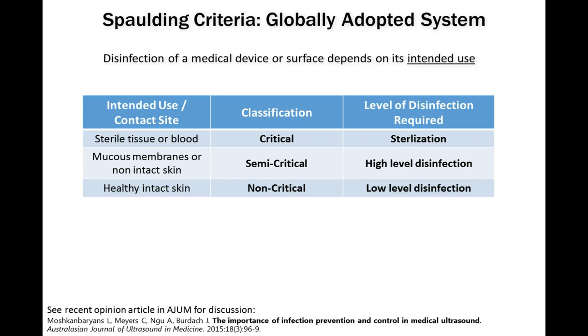Now, most areas of the world adopted the system based on the Spaulding criteria, which was written in the late 1950s. Disinfection of a medical device or surface depends on its intended use. You can look here in our little table at the intended use or contact site, classification, and the level of disinfection required. If the contact site is sterile tissue or blood, it is a critical site and requires sterilization of the equipment used. Mucous membranes or non-intact skin are classified as semi-critical, and they require high-level disinfection. And healthy intact skin is a non-critical classification, and it requires low-level disinfection.